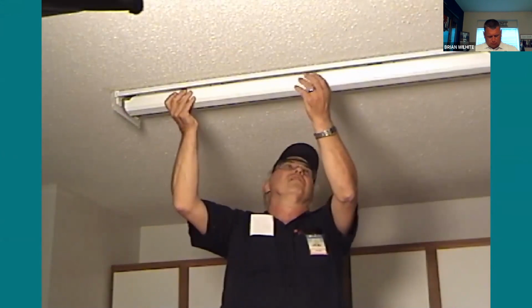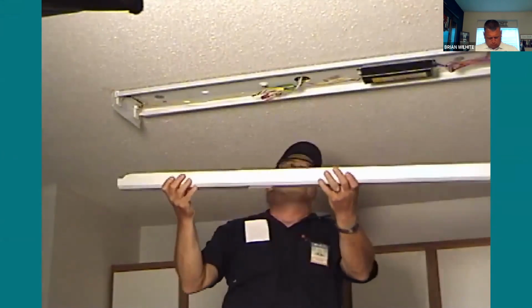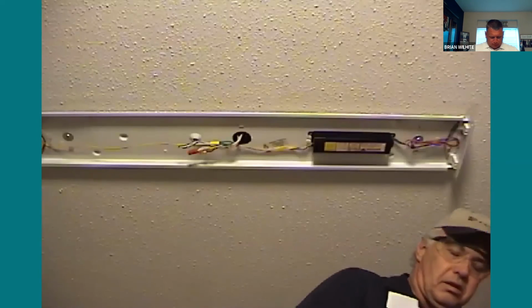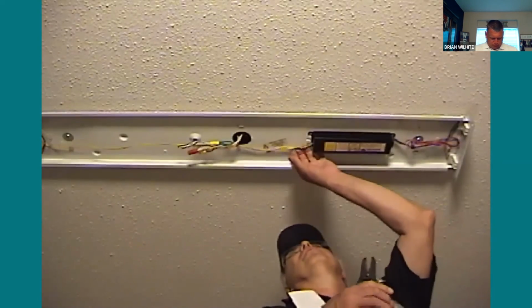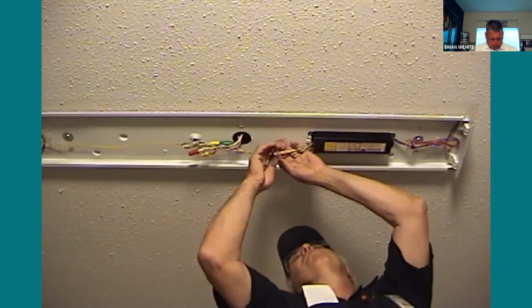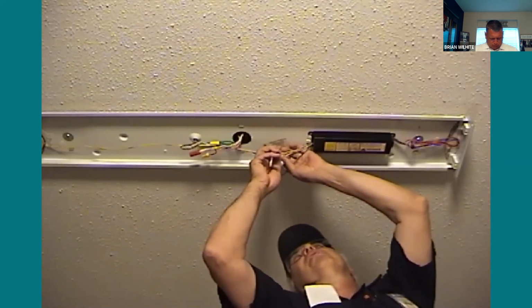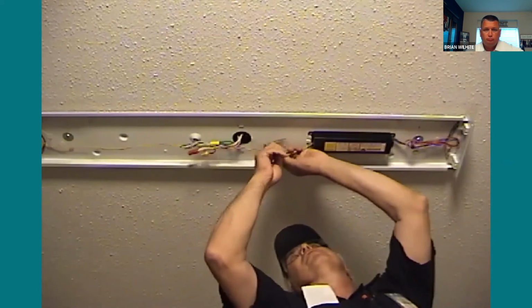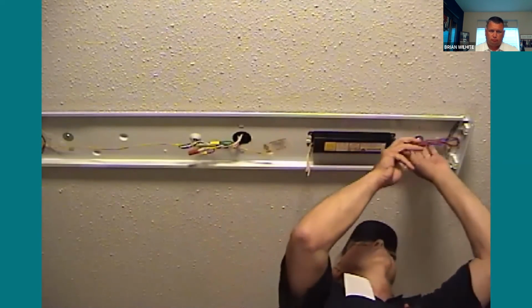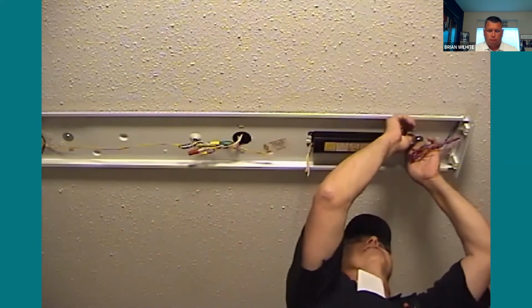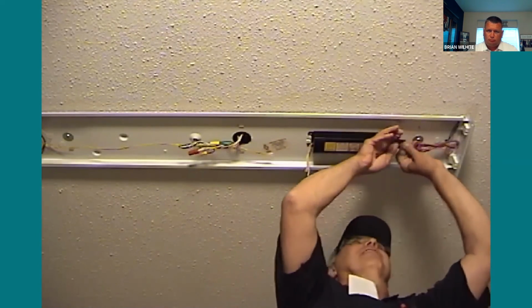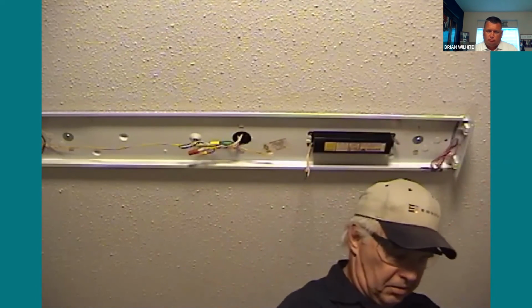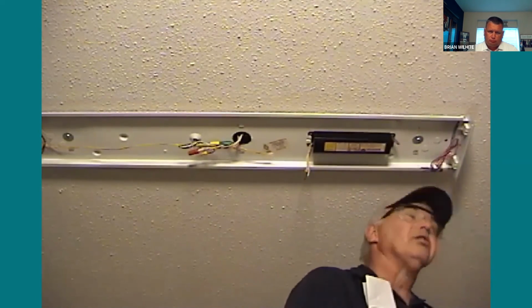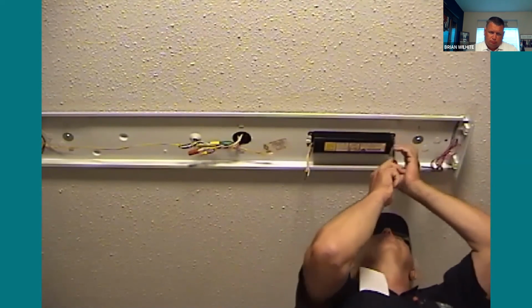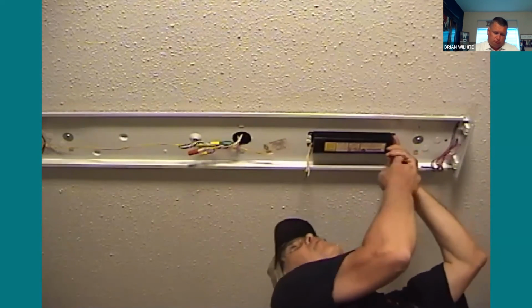Remove the ballast cover panel, and that will expose the ballast and the wiring associated. The next step is to cut the appropriate wires and remove the ballast. This is after the power has been secured properly using lockout tagout. Now the wires have been cut. The screws on each end will be removed to allow us to replace the ballast.